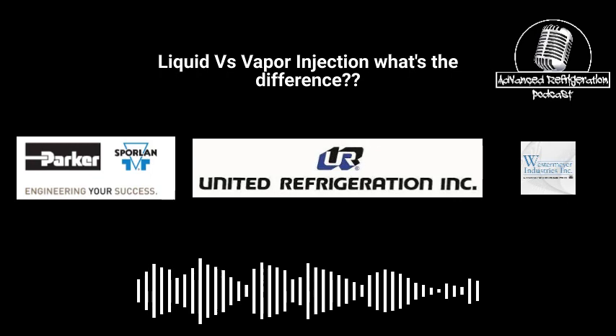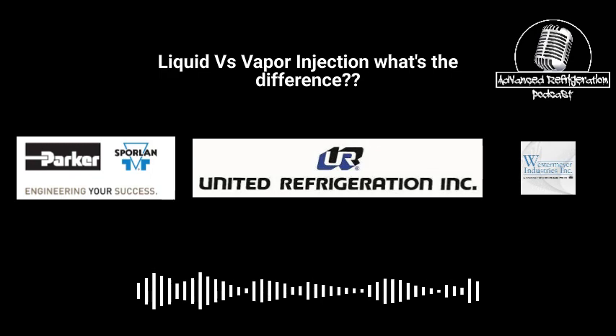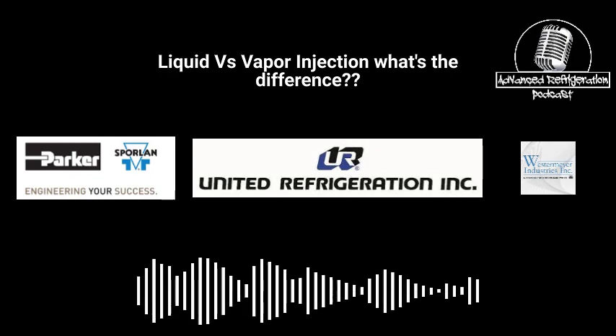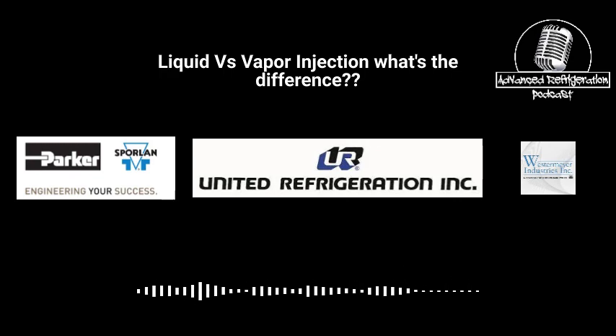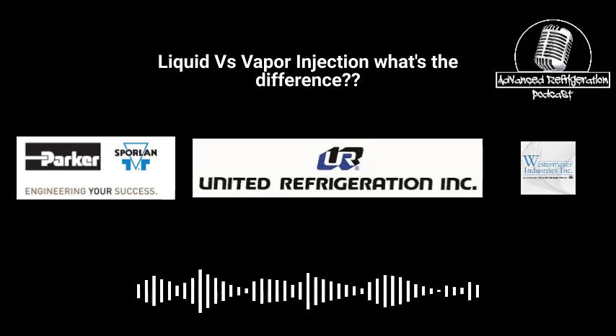Then the next number that you'll see will be the size of the valve. So like on the compound compressors, it'll be FV-1 and then dash. And then the next number will be either the 190, 210, or 230, which is telling you the temperature at which it's trying to control off the discharge line.